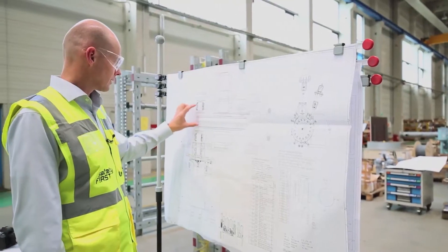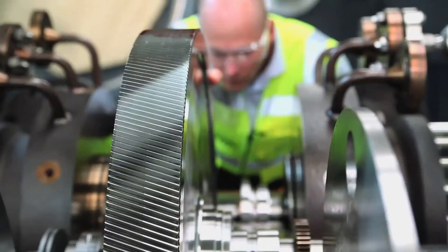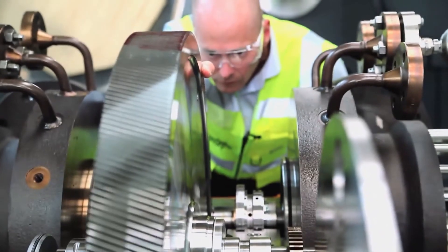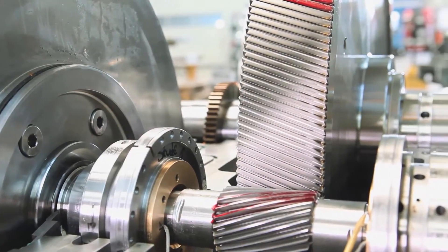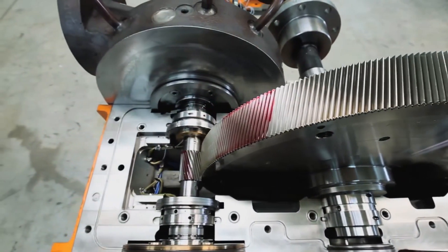This machine is a real workhorse. One of its key features are the dynamic dry gas seals, which minimize leakage. They release 35 times less CO2 than standard carbon ring seals. Add to that our integral gear technology, and you have a perfect package for the high rotor speeds and high pressures involved in this application.